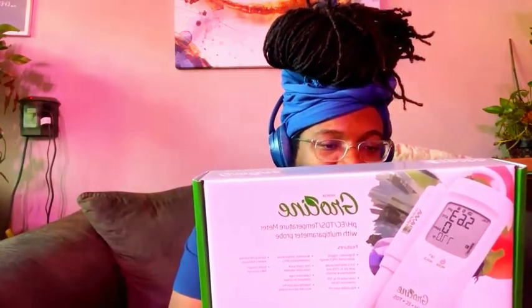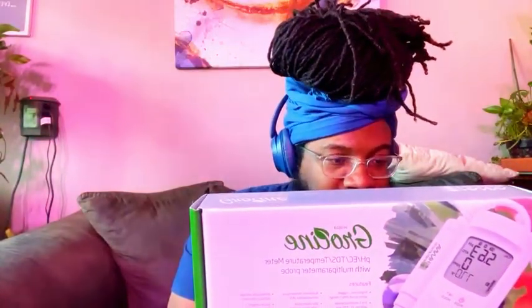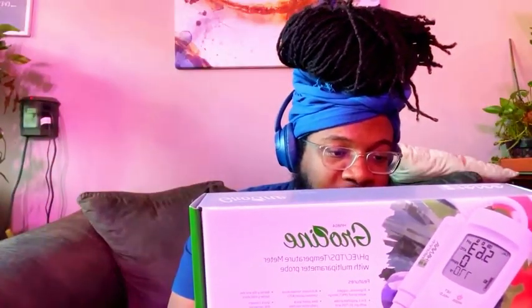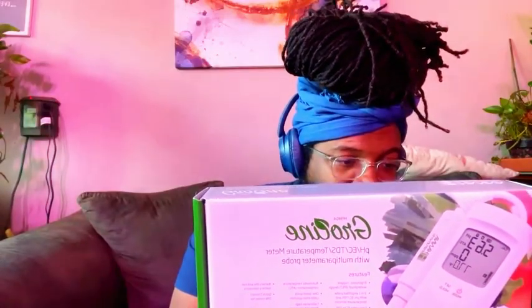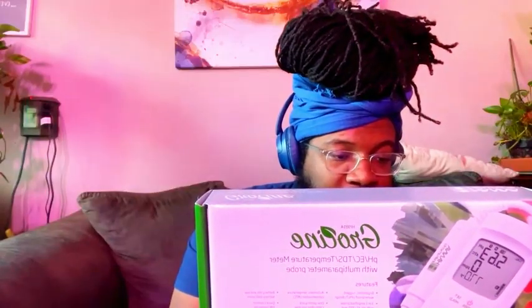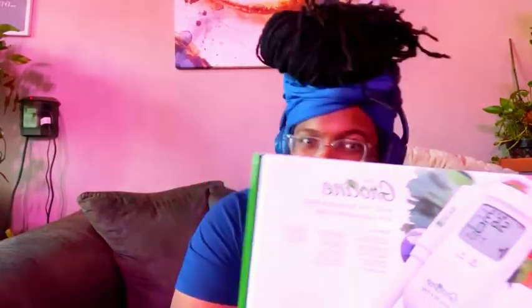You have automated calibration. EC range is from 0 to 6 millisiemens with accuracy of plus or minus 2%, which is beautiful. Dissolved salts in parts per million, 0 to 3,000, and 0 to 3,990, depending on the conversion factor, I should say, not the temperature. And then the temperature from -5, which is ice, to 105 C, and 23 degrees Fahrenheit to 221 Fahrenheit. So this is beautiful. For battery life, they say 600 hours of continuous use. So you may use this for 10 minutes maximum at any given time.